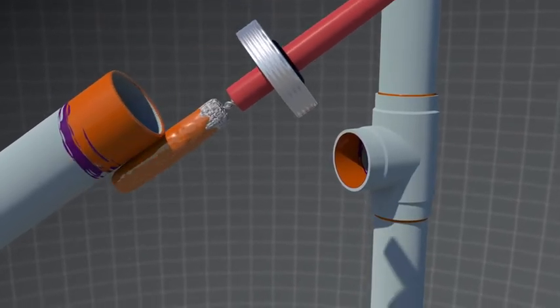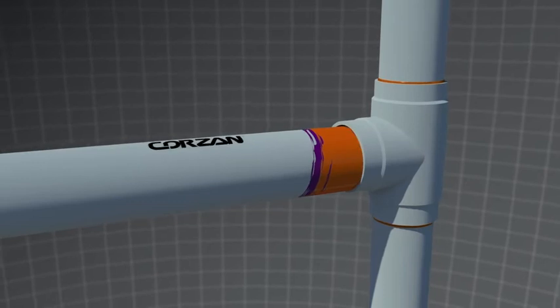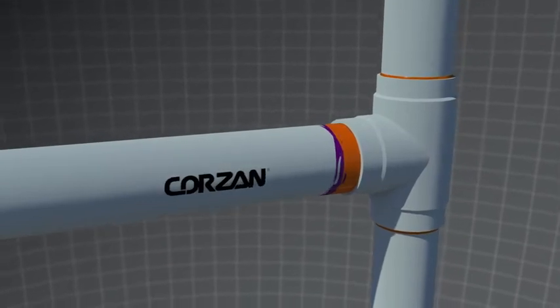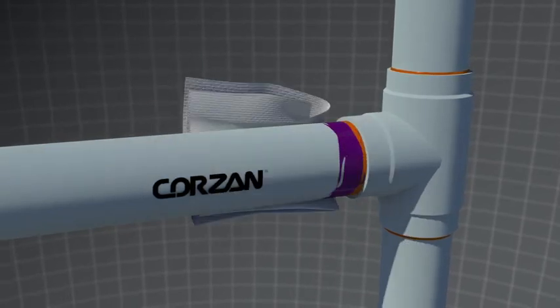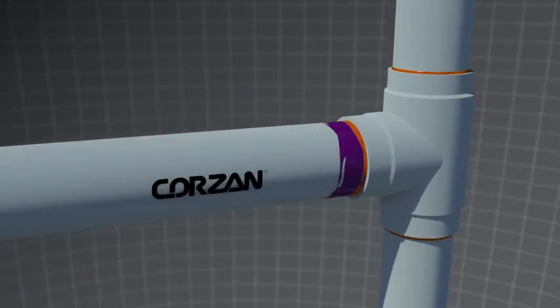Insert the pipe into the fitting while turning a quarter turn or approximately 90 degrees when possible. Hold for 30 seconds to allow the joint to take. Finally, wipe excess cement from the outside of the pipe.